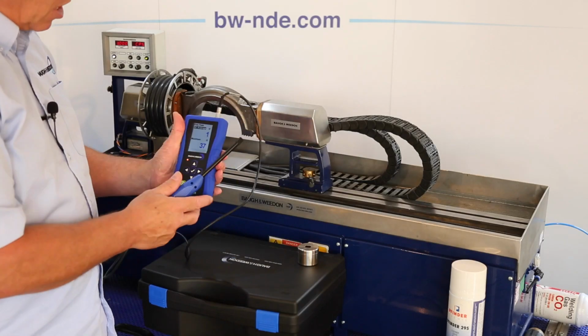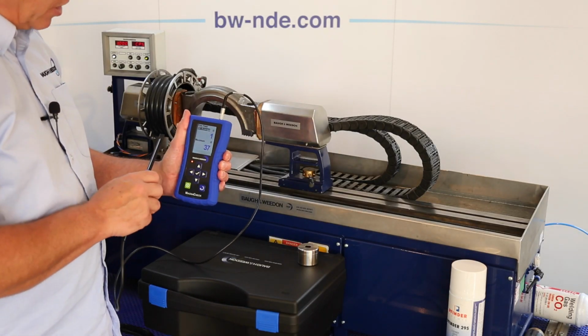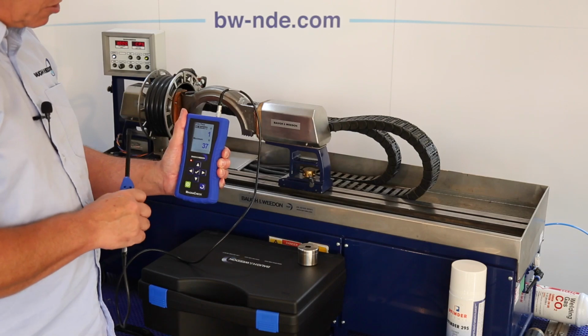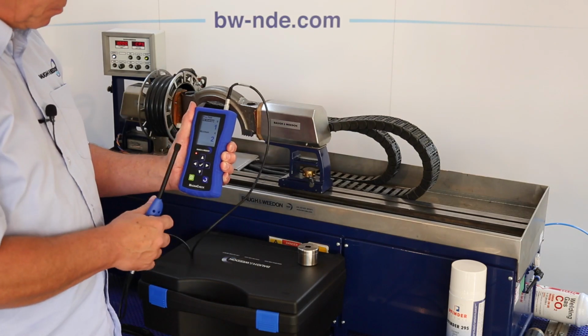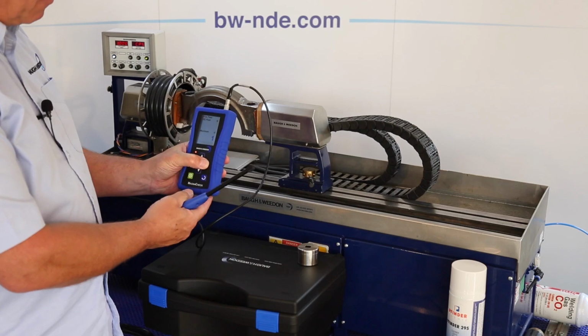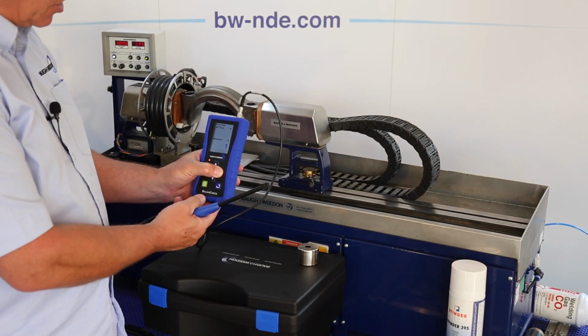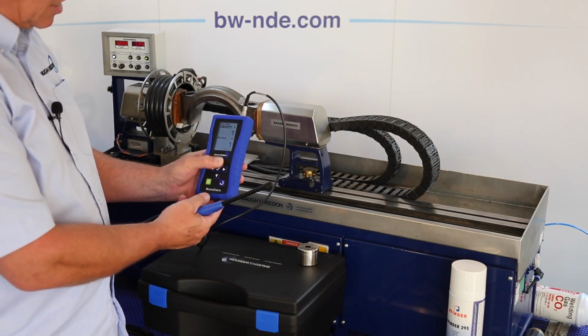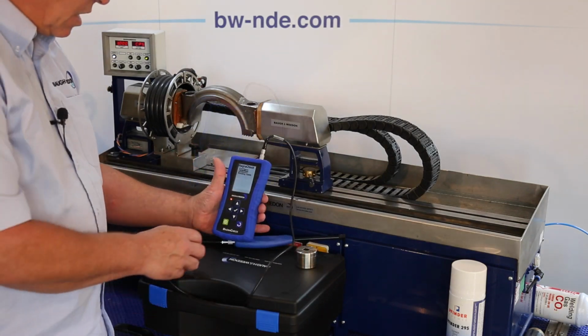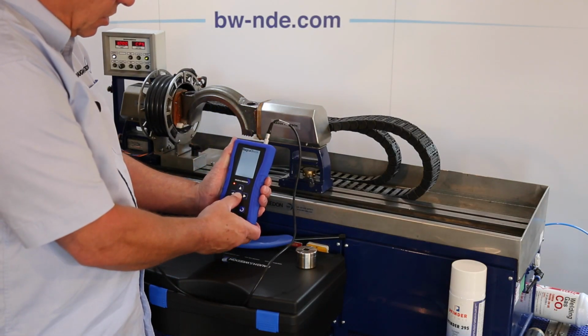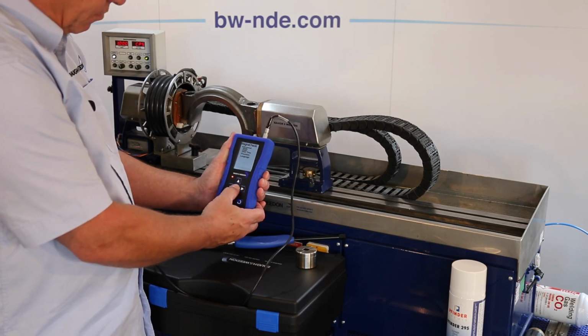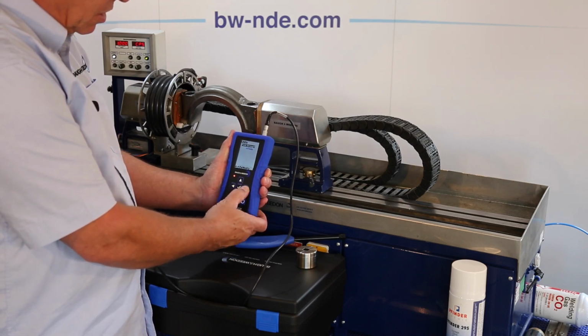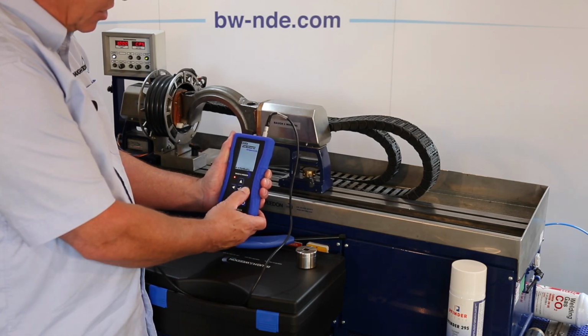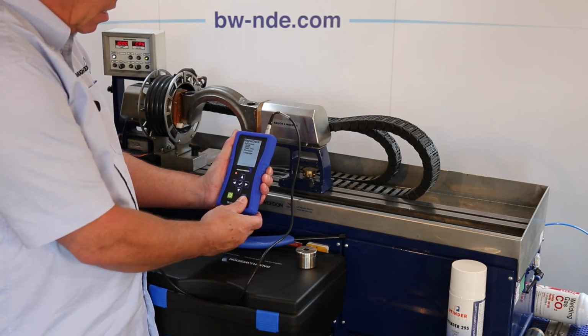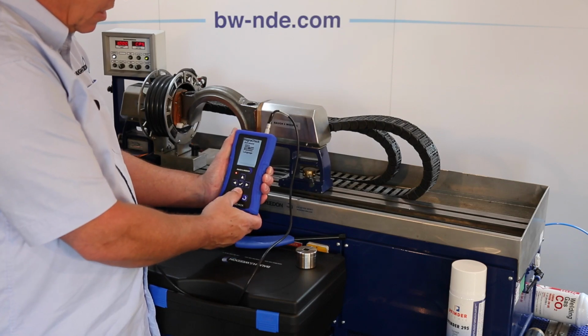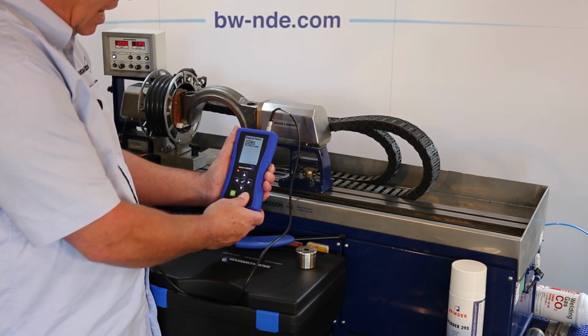The bottom screen will read the highest level achieved, the top screen is live. The amount of time this holds can be adjusted in the settings. You can measure DC average, DC peak, RMS, AC peak, AC average. In the advanced settings, you can adjust the units: Gauss, Tesla, amperes, the hold time, the language.